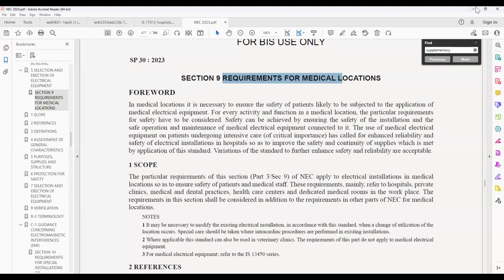Then, in the National Electrical Code, you can find this kind of table. On the left side, you are seeing different kinds of medical locations. For example, anesthetic room. You can find group 0, group 1, group 2. So anesthetic room is classified into group 2. So you need to have the safety measures recommended for that particular location. Like this, you can find the recommended table in NEC where each location is very clearly classified. For example, a group 2 location. In a group 2 location, medical IT system. I have just copied from the National Electrical Code: in group 2 medical location, a medical IT system, including medical isolation transformer and medical isolation monitors, shall be used for final circuit and where the same final circuit is connected to ME equipment or an ME system located within the patient environment.